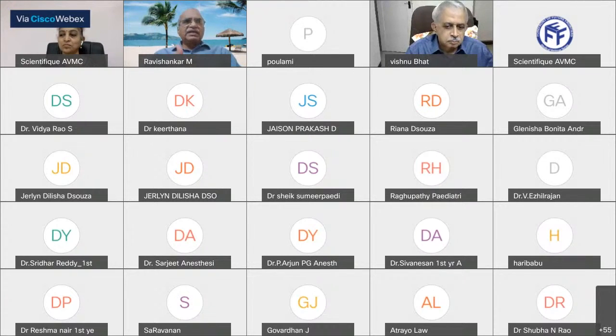A few centers have definitely changed over to air and oxygen and totally stopped using nitrous oxide. But the advantage of using nitrous oxide outweighs those losses, because in terms of expense and smoothness, people are slowly coming back to say we will use nitrous oxide but not release it into the atmosphere. That is why the low flow system is used, minimizing the amount of nitrous oxide to only the level the patient needs, rather than indiscriminately pushing it into the atmosphere.